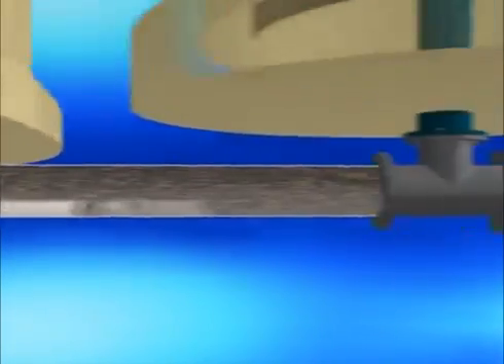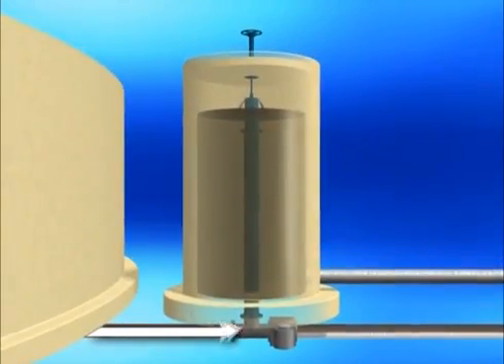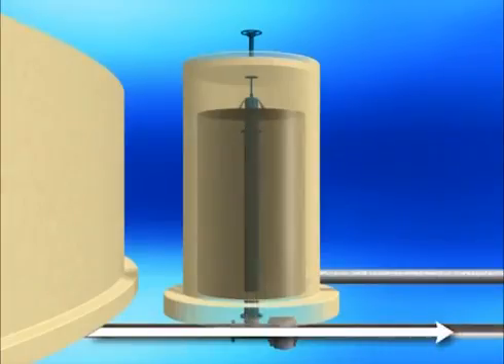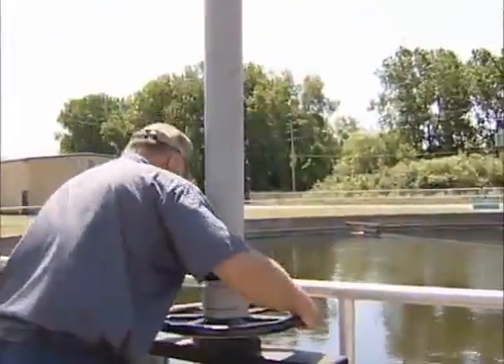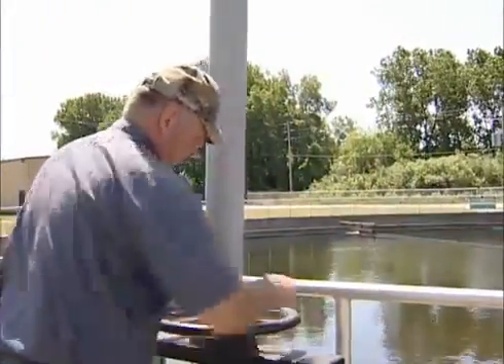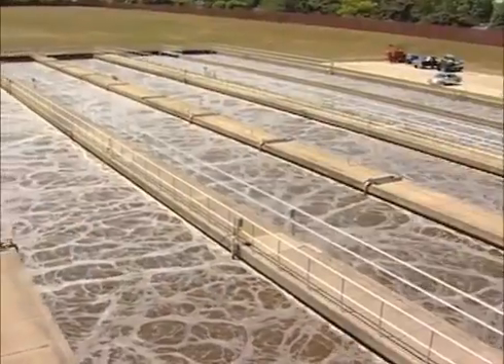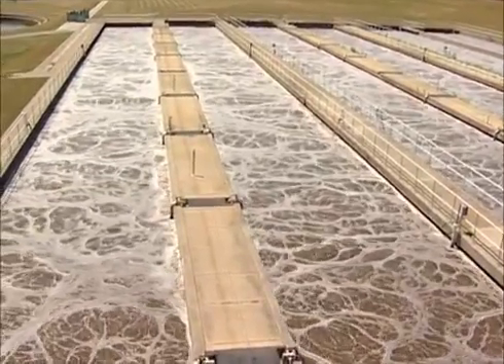Solids collected in the unitube header exit through the sludge removal system and are controlled by hydraulic head differential or pumping external to the basin. Rapidly removing solids ensures better plant performance because solids are quickly returned to the aeration system where they break down the organic matter, and they are not allowed to accumulate in the clarifier where they can resuspend and lead to degraded effluent performance. Also, denitrification is prevented and biological phosphate is not released.